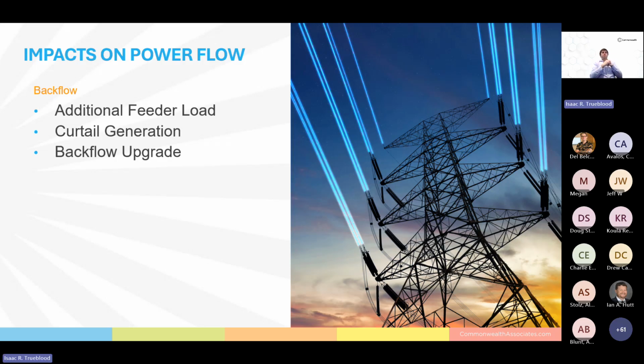Additionally, this can flip the relationship between a transmission provider and a distribution owner from purely buying relationship to a buying and selling relationship. These relationships are based on contracts and agreements that can be difficult to untangle and renegotiate. There are a few ways to mitigate backflow conditions. The first is to simply limit the amount of distributed energy resource generation on that feeder. If the distributed energy resources never generate more power than the feeder load is requiring, there will not be a backflow condition.